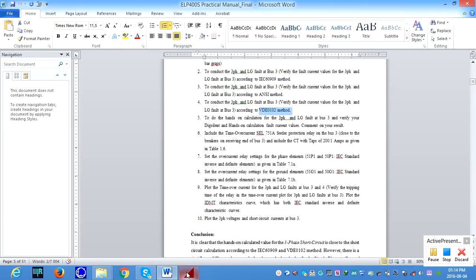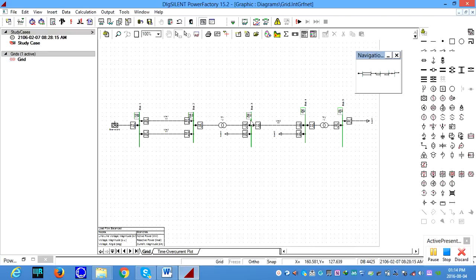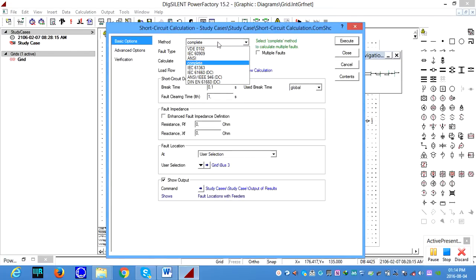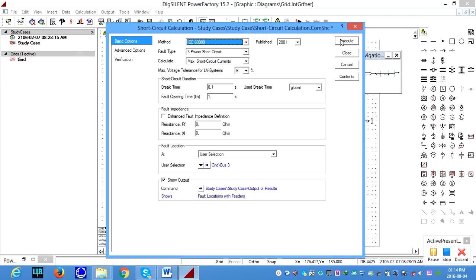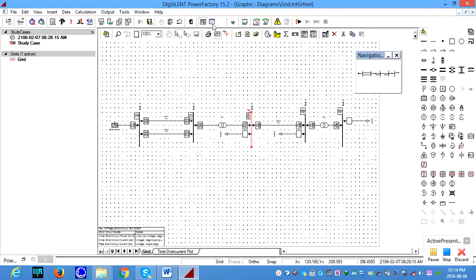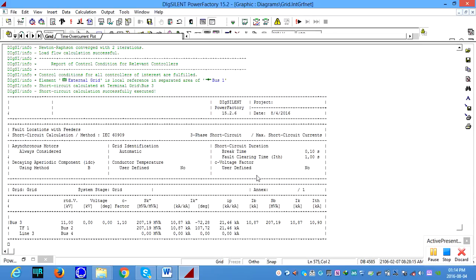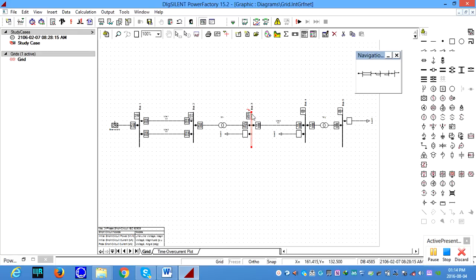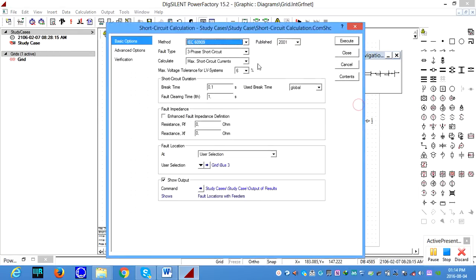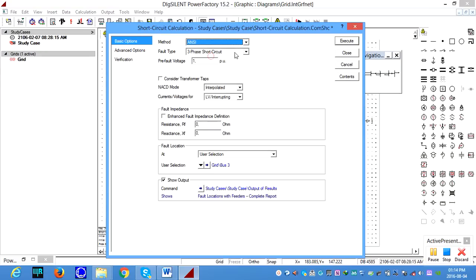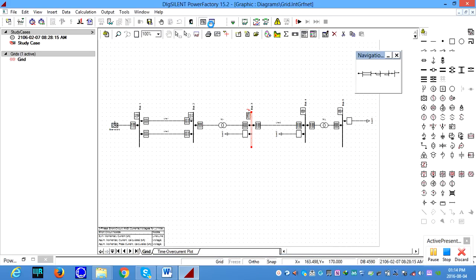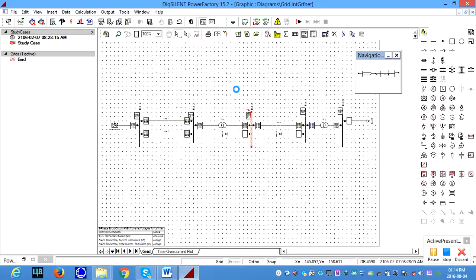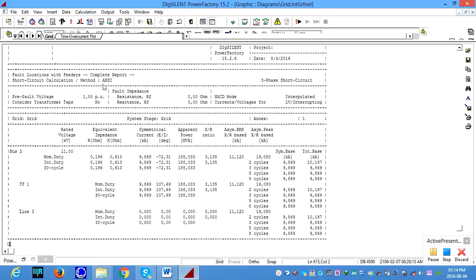Okay, first we can do that. This is bus 3. You can right click, calculate, short circuit. There are different methods. Either you apply the IEC method and execute the fault and see what the fault current value is. You can go to the output window, and you can see you applied your short circuit based on the IEC method and find out the results. Next, we need to change to a different short circuit method, either the ANSI method, execute, and you can validate this is your ANSI method, okay, and the results for the ANSI method.